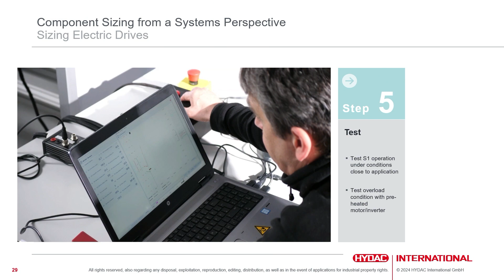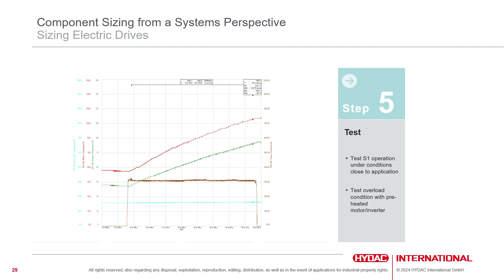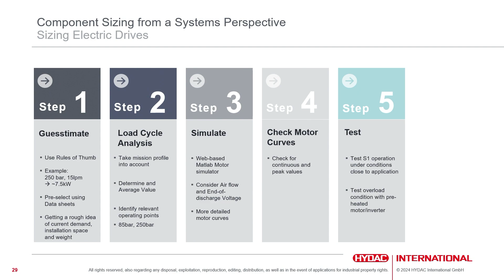We also did other tests, for example for peak power demand, checking how long we could sustain that peak power demand. The result was that even with a preheated motor—one that had been running continuously before—we could run at that peak operating point for up to 6 minutes. So it's not really a single peak; it's some kind of S9 motor profile that we can cover with that.